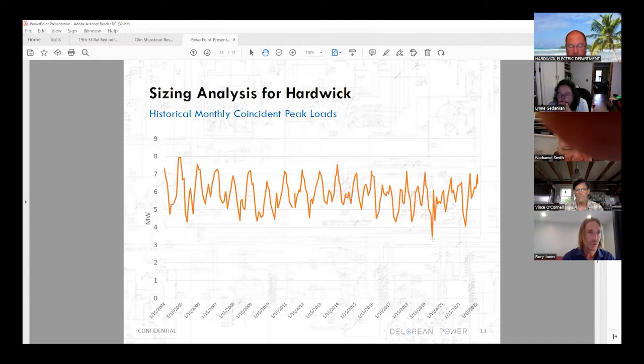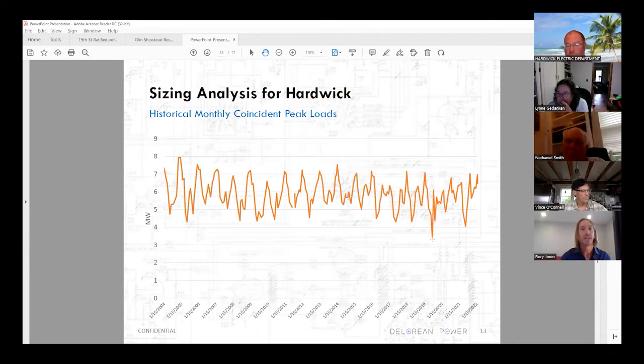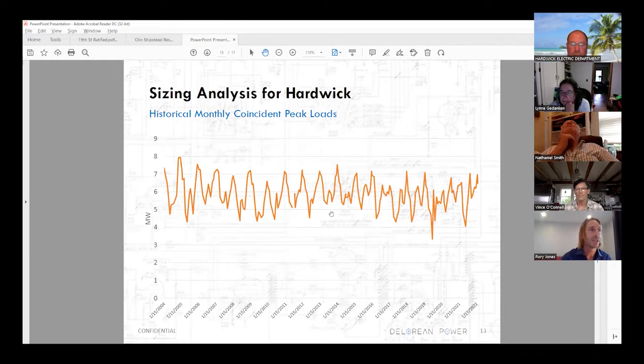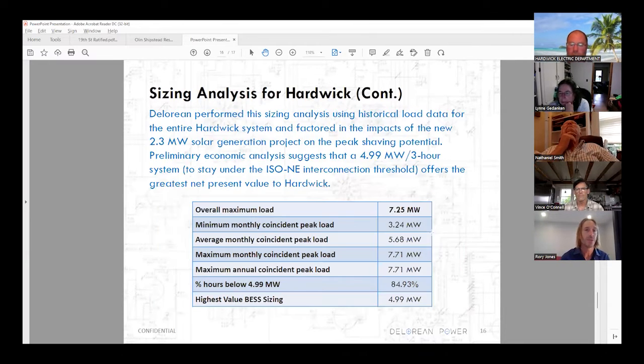That's not exactly true, because you have scale economies on the investment itself, mobilizing to the site, the battery supply, and at all the other times you're having the ability to tap into more megawatts. So it's a bit of an optimization on net present value of a slightly lower cost per megawatt system and its ability to always be able to hit those peaks with full nameplate capacity.